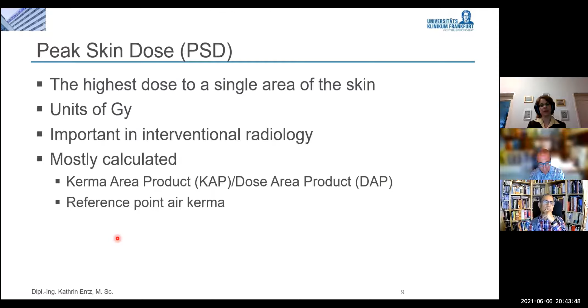In theory, obviously, you could measure the peak skin dose by placing a range of dose meters on the patient before the examination, but that is usually not done. Most of the time, it is also calculated by using the values you get from your system, like the Kerma area product, KAP, or the dose area product, DAP, and again, multiplying it with conversion factors, or what is also quite often taken is the reference point air Kerma, which is a good estimation for the peak skin dose. Just a short revision on what is actually the reference point air Kerma, or where is the reference point. This is the definition according to the International Electrotechnical Commission. There are also some other definitions, but this is the most commonly used one.